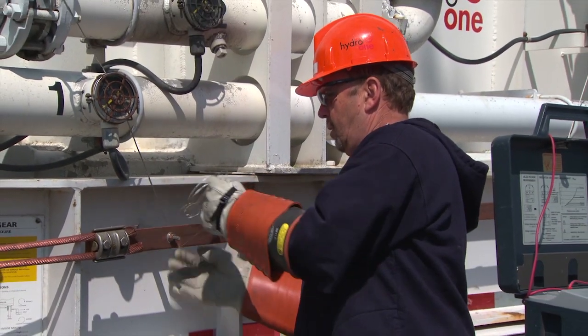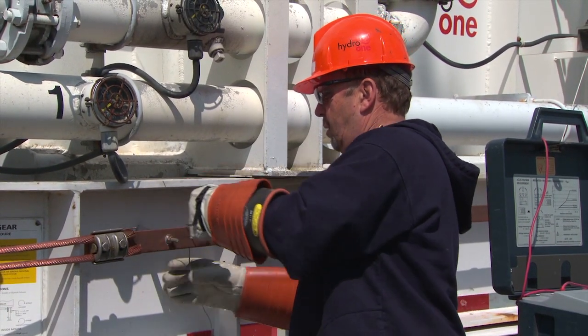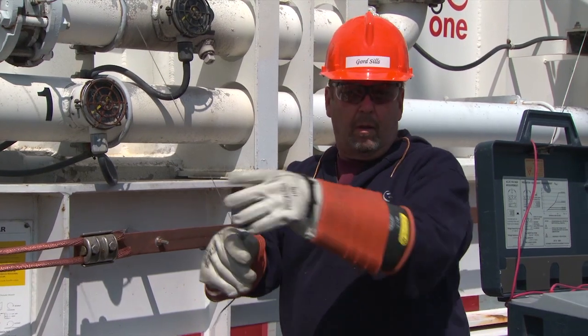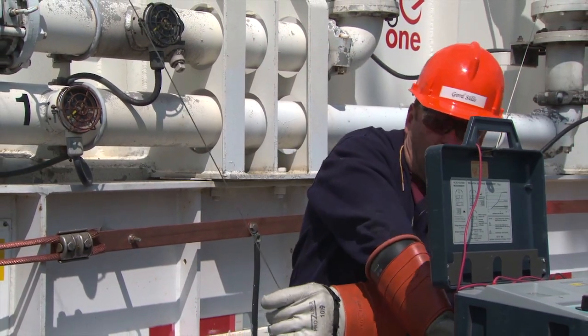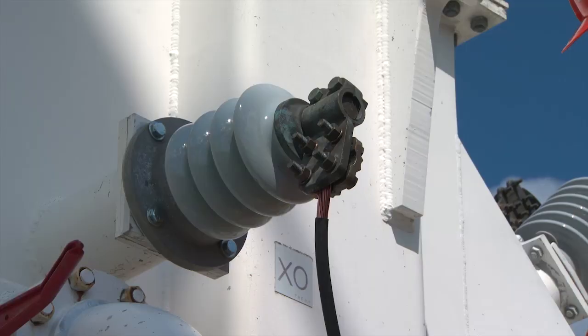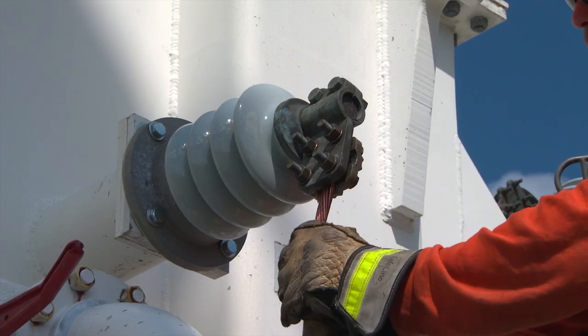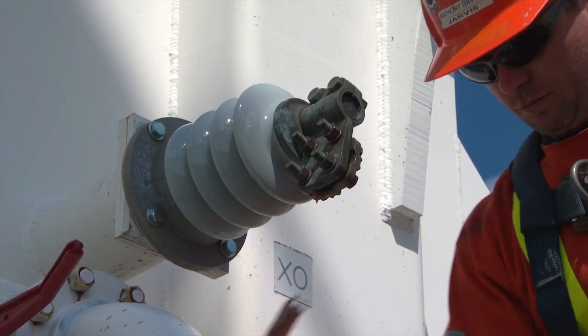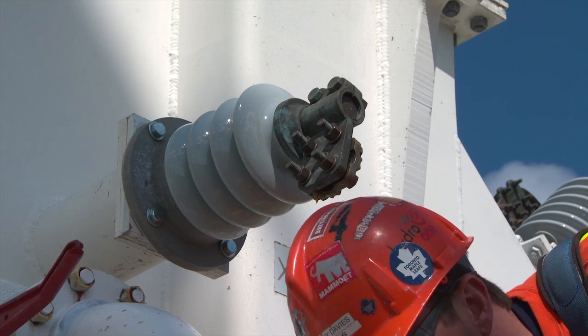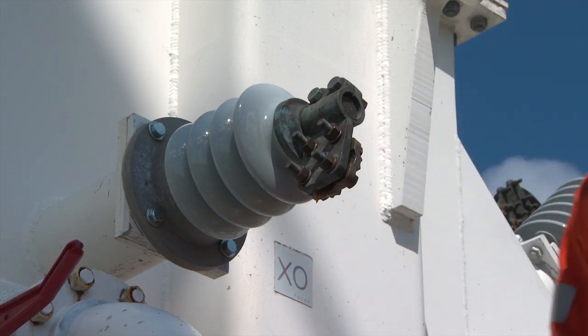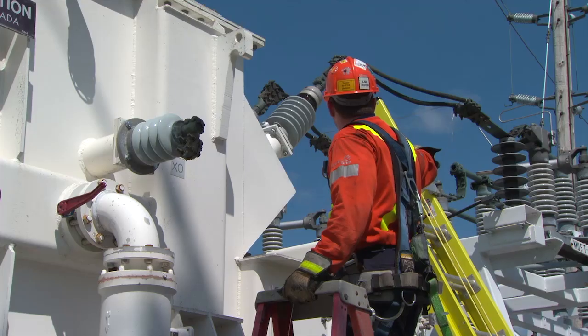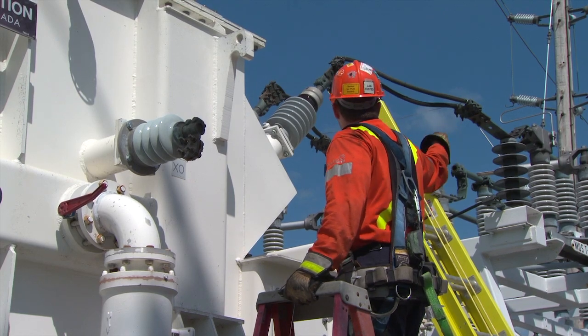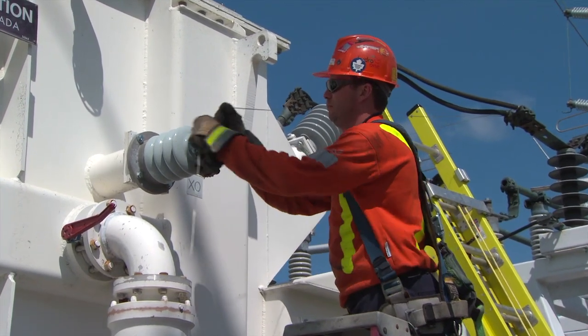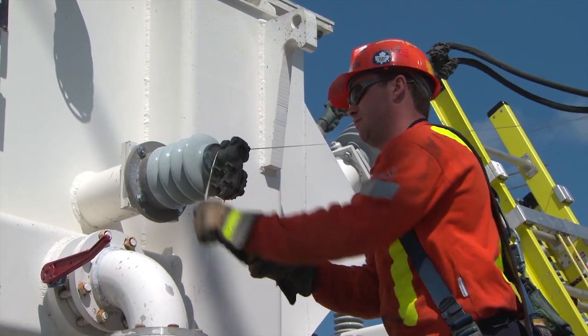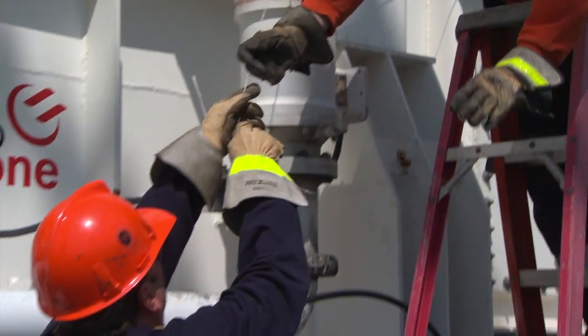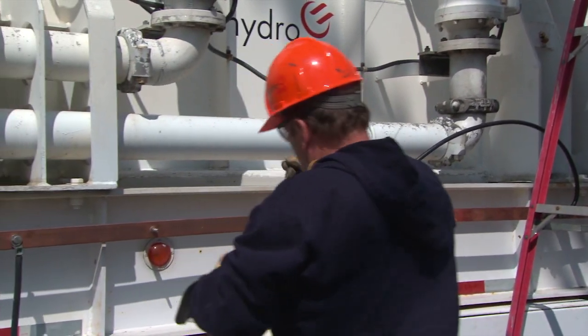When moving the test leads and wire braid, rubber gloves should be worn in order to protect yourself from potential capacitance charge. Before you begin, ensure that the high voltage and low voltage switch or reclosers are open and disconnect the XO bushing. Using wire braid, tie the 3 high voltage bushings together and short to ground. Then connect all 3 low-voltage bushings together with the XO bushing and short to ground.